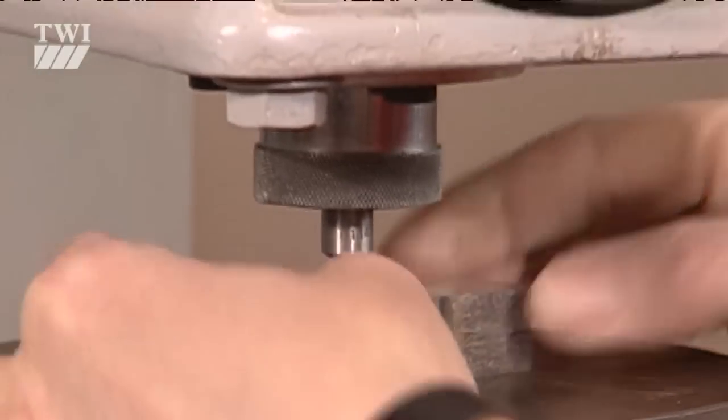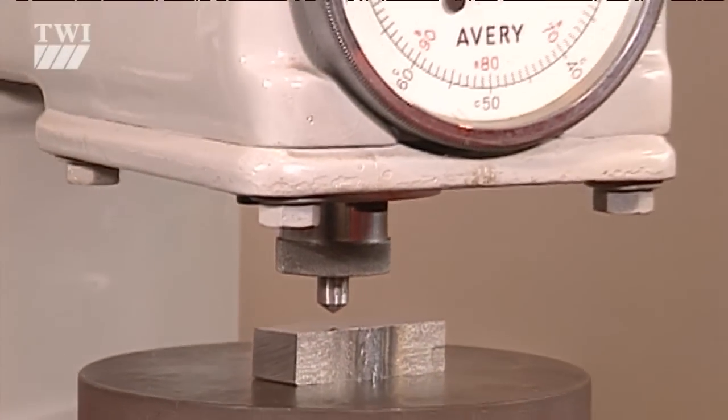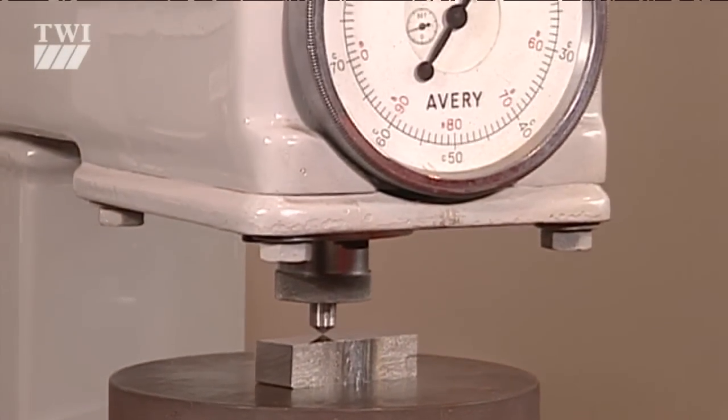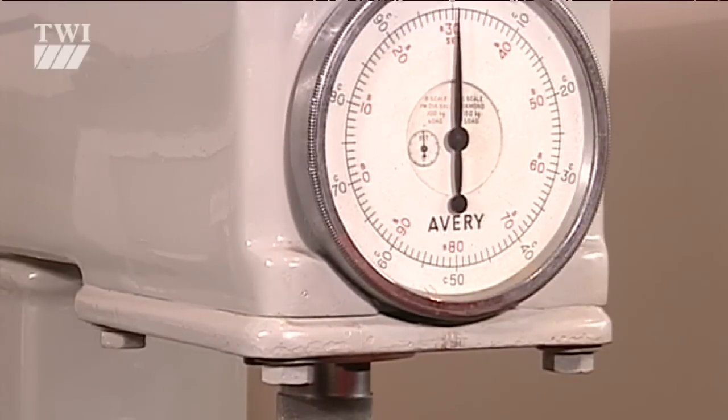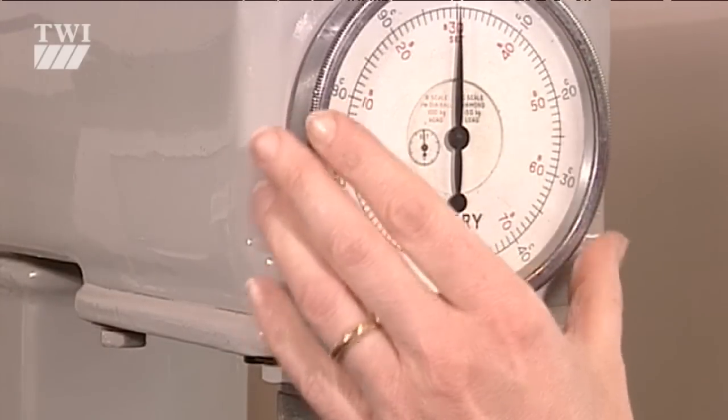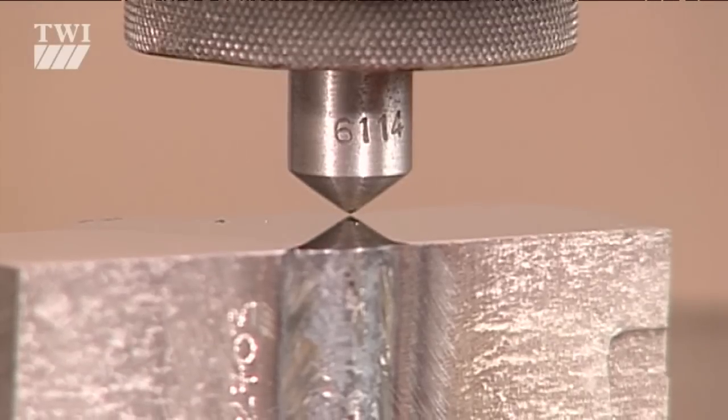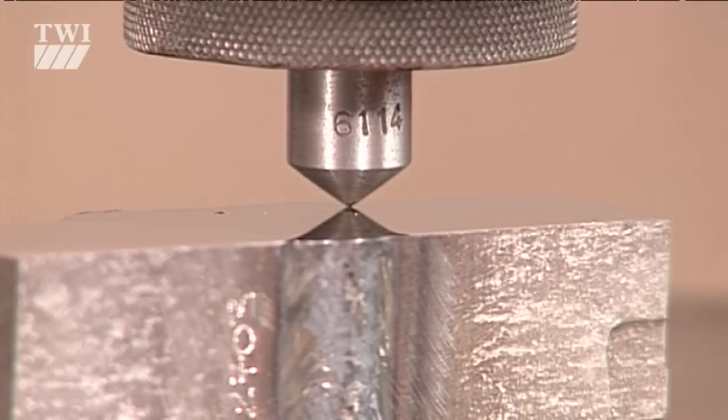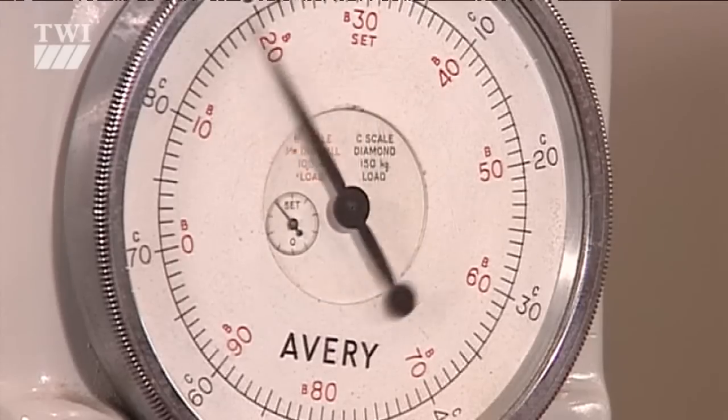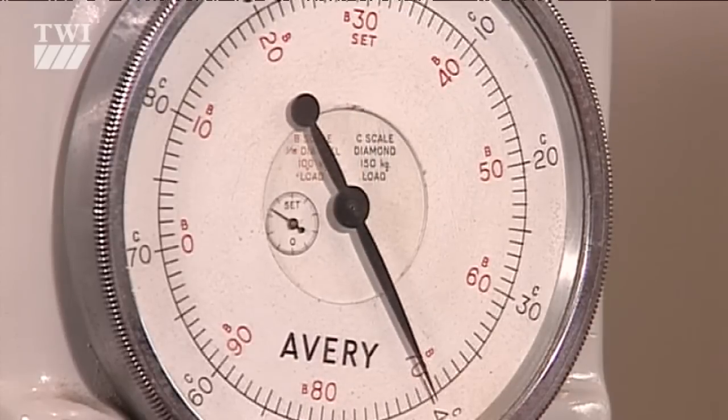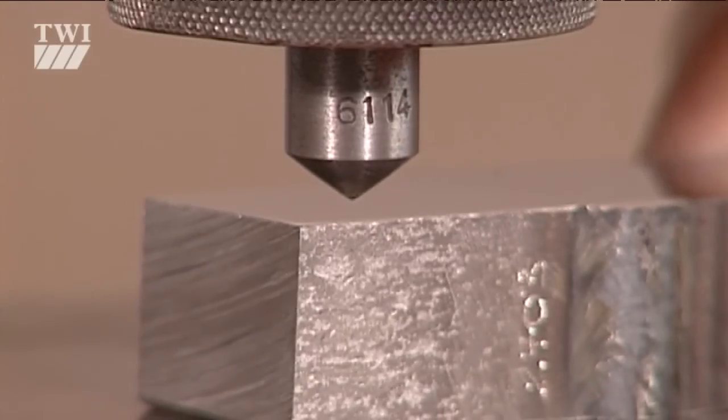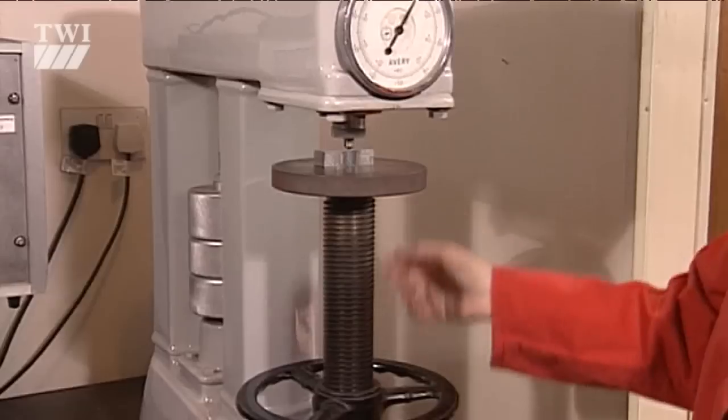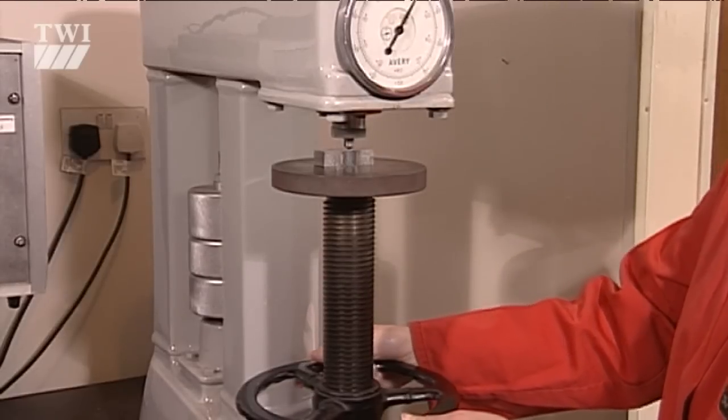The Rockwell hardness test, named after the American Stanley Pickett Rockwell, works on a similar principle, with a conical indenter, but uses two applied loads. The permanent increase in penetration depth is used to calculate the Rockwell hardness number. Different loads are used for materials with different hardnesses. The most common scales are Rockwell B and Rockwell C hardness.